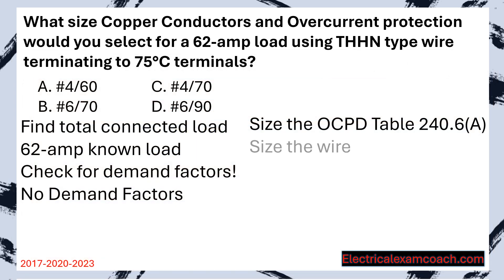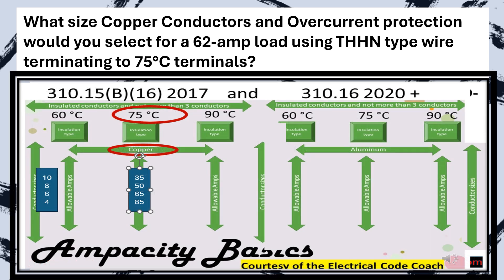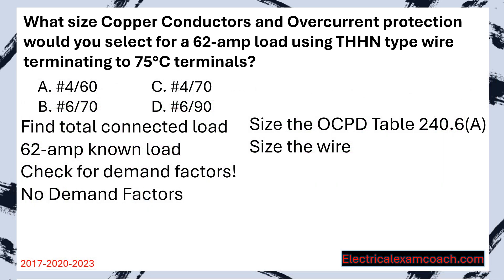Now we can size our wire. For that we head to our primary ampacity table. We're on the copper side because it's asking for copper, and we're in the 75 degrees C column. We slide down and find a wire that covers the known load, and we find that we're going to have a 6 gauge wire on a 70 amp breaker.